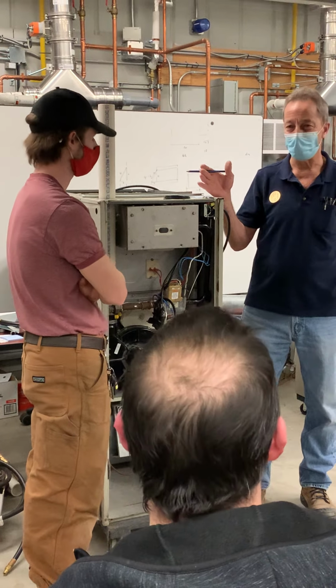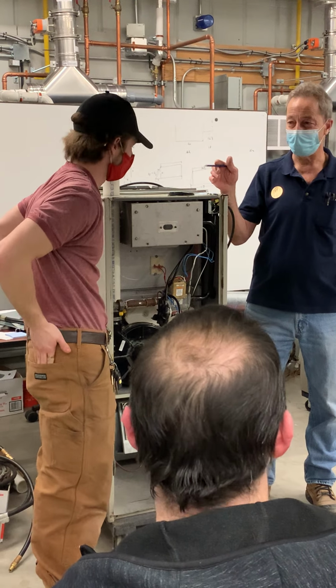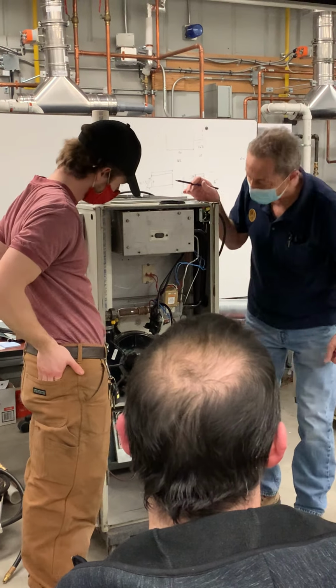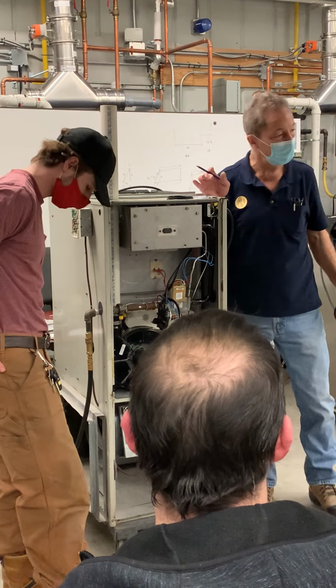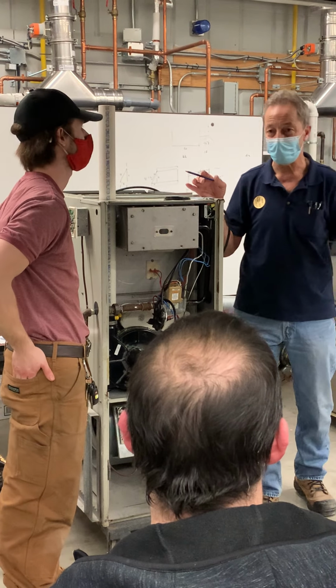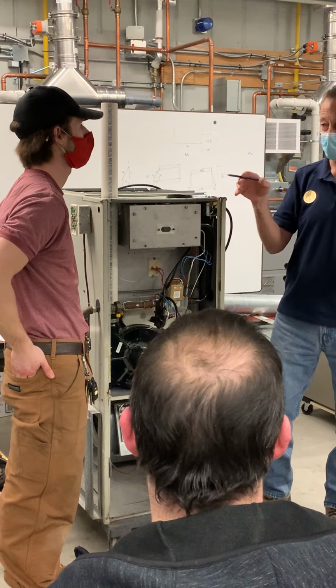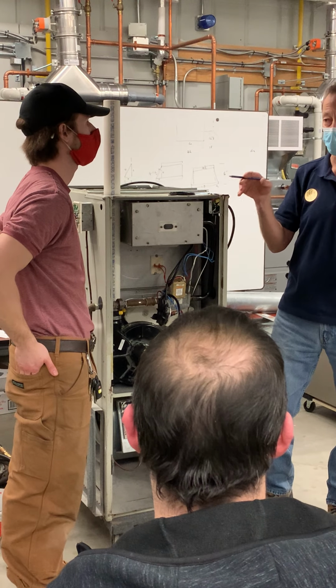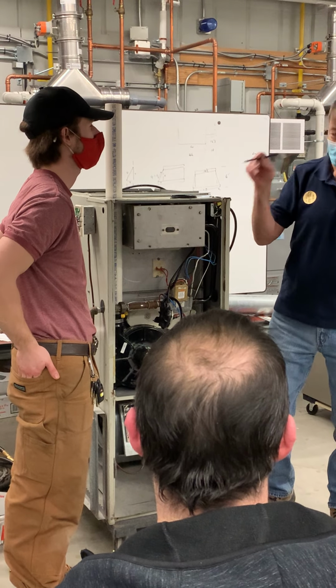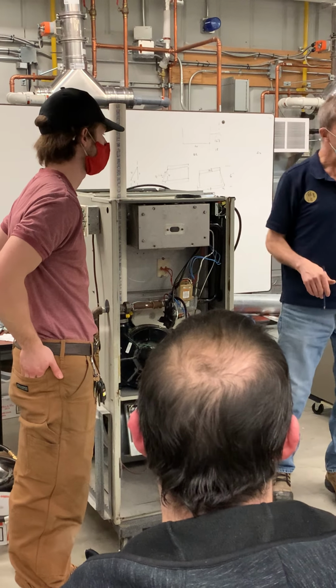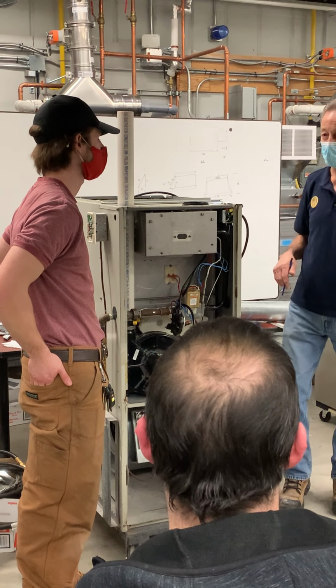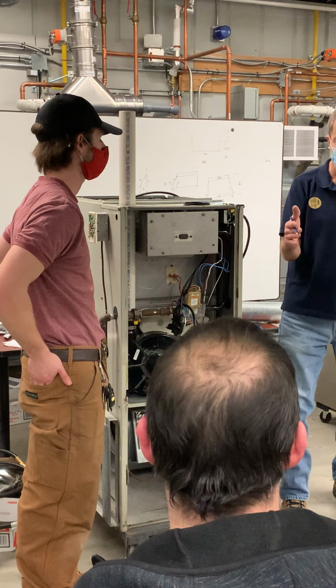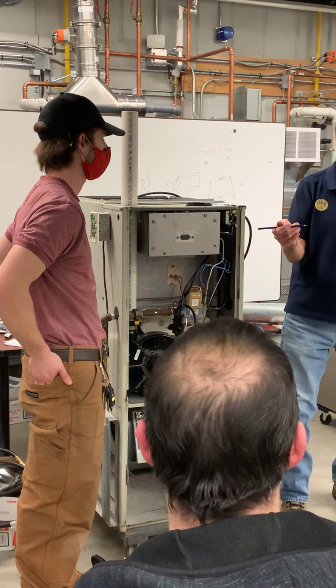And why do I dwell on that? Why do I bring that up? Because you're smart. You know that if I'm looking in here, I see the pilot flame, I see the HSI glowing. What do you suspect the problem is if it doesn't progress any further in the sequence? Of not sensing the flame. Thank you, it's not sensing the flame. If it doesn't sense the flame, it won't shut off the HSI. It'll go for the trial for ignition. What's the trial for ignition, please?